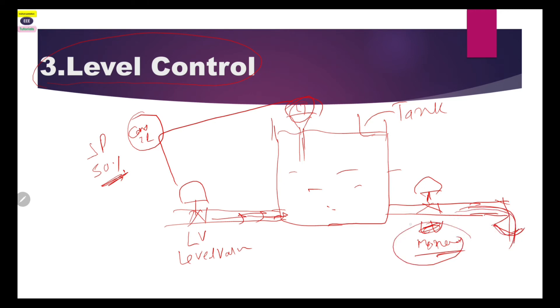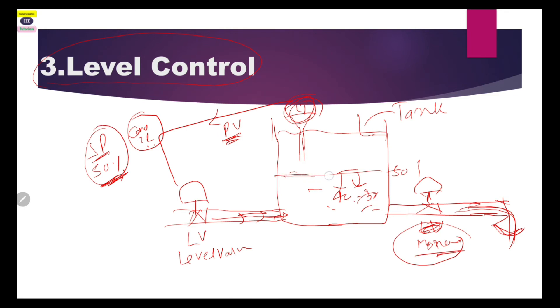We have to maintain 50 percent level of this tank. If the manual valve is opened, the level of the tank will reduce. Whenever the level goes from 50 percent to 40 or 30 percent, the level transmitter measures the actual current level and transfers the PV value to the controller. The controller compares this PV to the set value, and automatically gives command to the valve to open or close to maintain the required level. This is how level control works in oil and gas and instrumentation engineering.